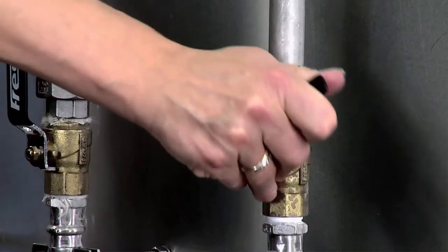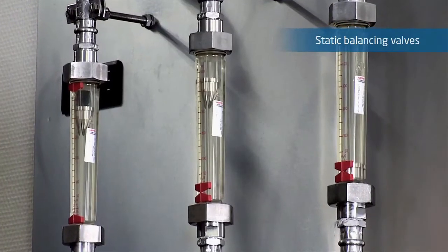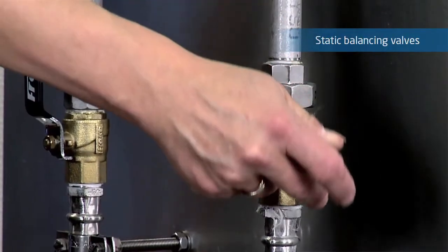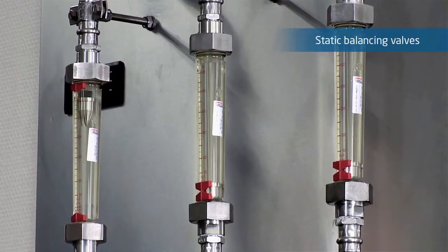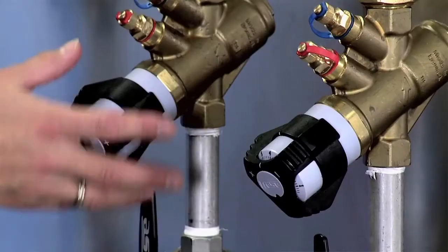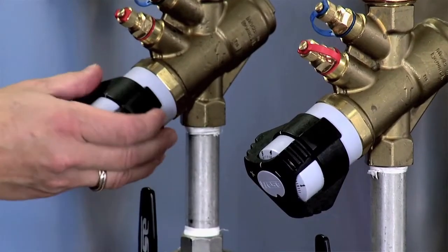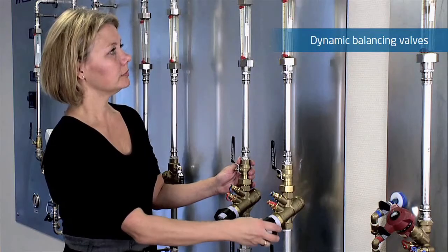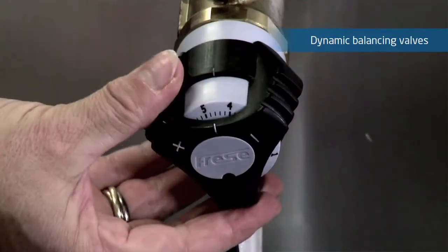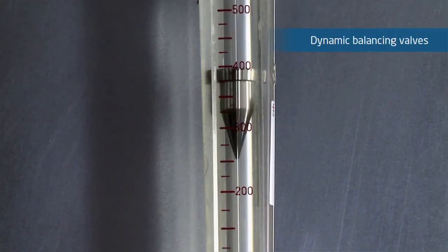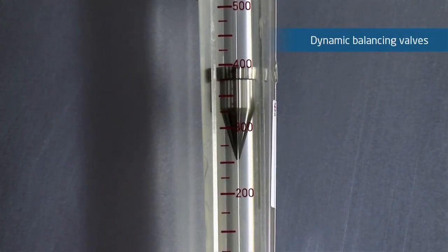The problem, though, is that the pumps speeding up and slowing down and the valves opening and closing causes all kinds of chaos in the pipe system. We need what we call pressure-independent devices, which can increase or decrease their characteristics or their resistance to control flow around the building effectively and efficiently.